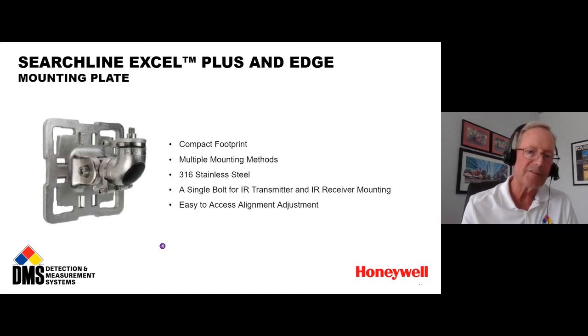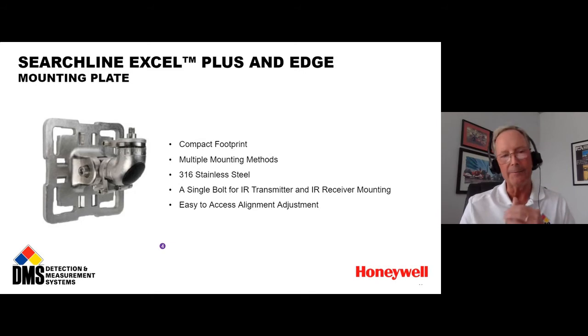Basically, you mount the Searchline Excel Plus receiver or source on top here. It bolts on with that single bolt, and there's a cap at the bottom you simply remove with a screwdriver. Although it stays in place with a supporting strap, you can access the Allen bolt from the bottom to tighten it and securely fix your source or receiver on top. It takes less than a minute to install the receiver or IR transmitter onto the mounting bracket.